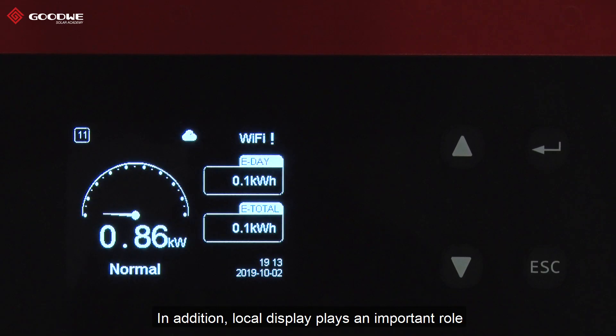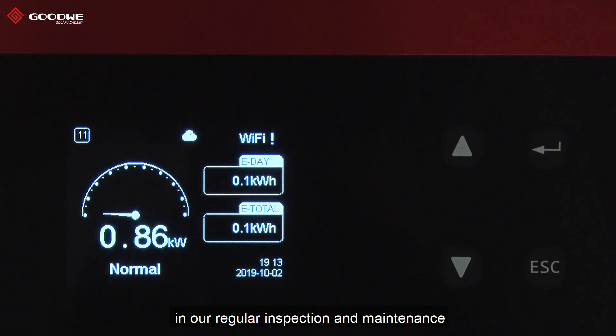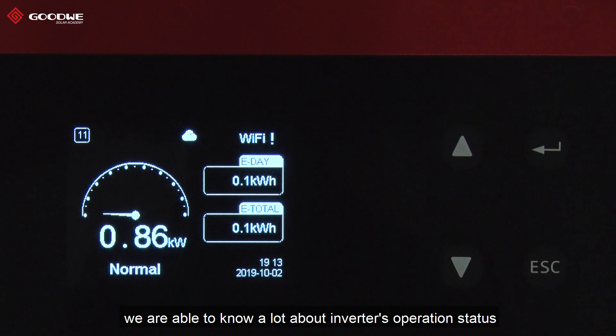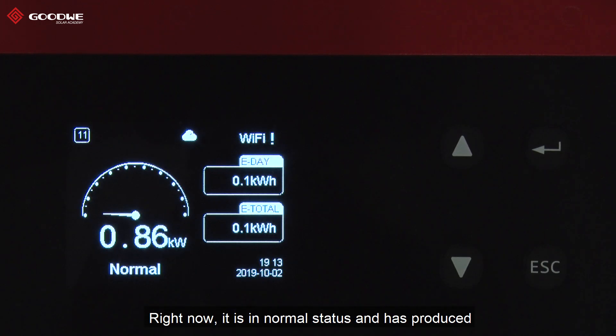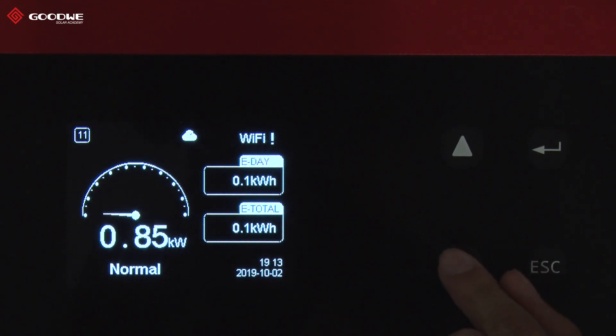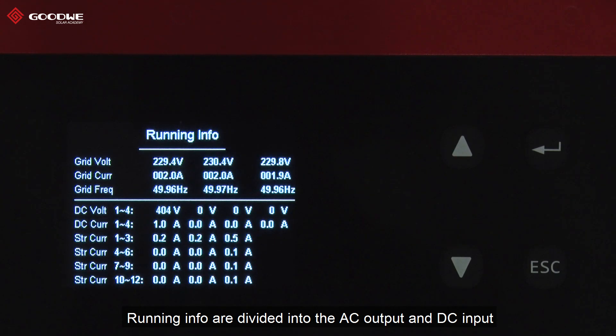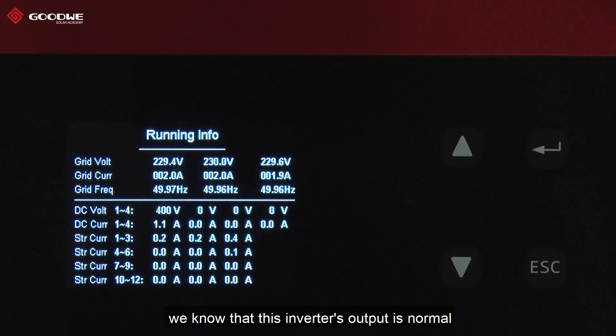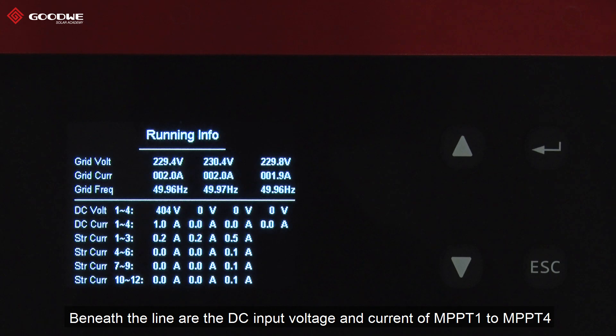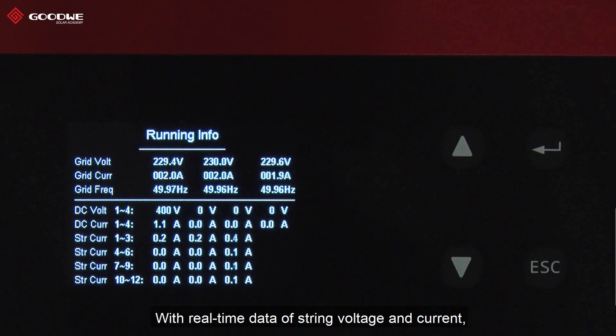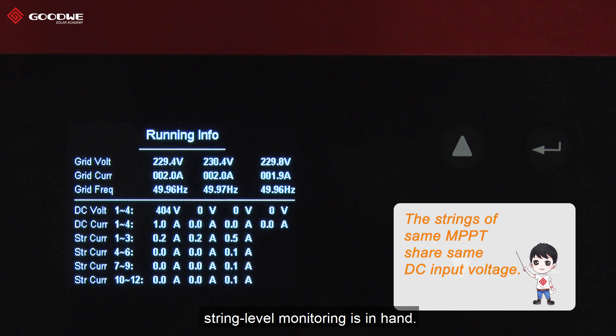In addition, the local display plays an important role in regular inspection and maintenance. From the homepage, Running Info, and History Data pages, we are able to know a lot about the inverter's operation status. Right now it is in normal status and has produced 0.1 kWh of electricity today. Total generation is the same. Running Info is divided into AC Output and DC Input. From the grid voltage, current, and frequency of each phase, we can confirm the inverter's output is normal. We also check the DC input voltage and current of MPPT1 to MPPT4. Since we only connected strings to MPPT1, there are inputs only from string 1 to string 3. With real-time data of string voltage and current, string-level monitoring is at hand.